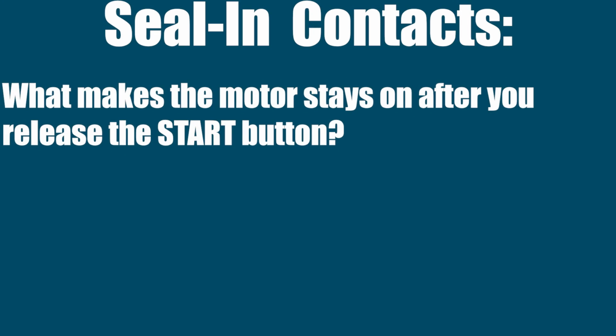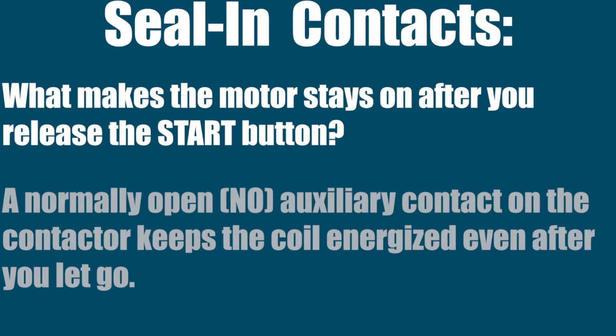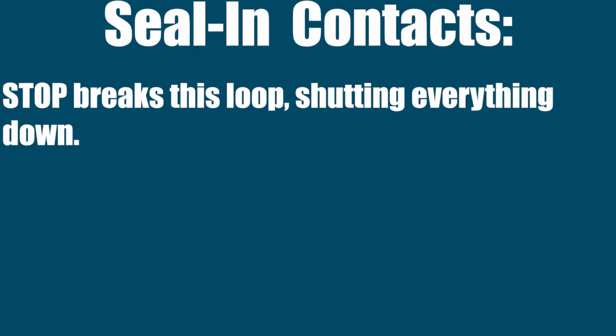Then you've got seal-in or self-holding contacts. This is what makes the motor stay on after you release the start button. That's the work of a seal-in contact. So a normally open, or NO, auxiliary contact on the contactor keeps the coil energized even after you let go. Stop breaks this loop, and this shuts everything down.